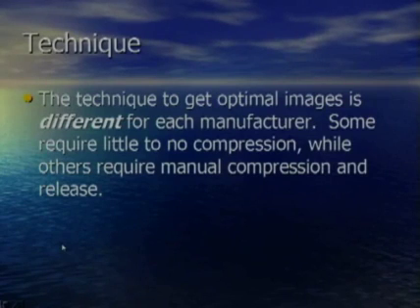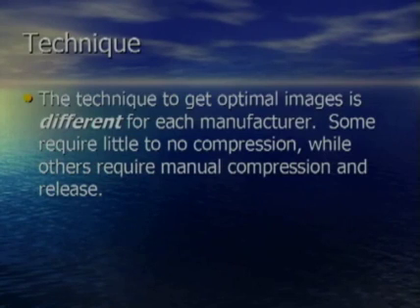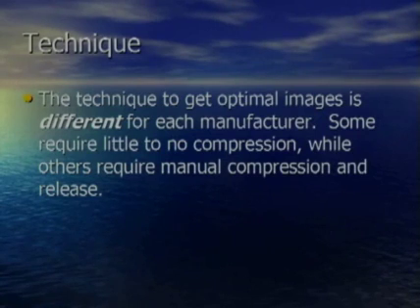Technique is very important in getting optimal images, and the technique actually changes based on manufacturers. Some manufacturers' equipment requires very little or no compression, while others require some manual compression and release to generate an appropriate elastogram. So one manufacturer's equipment may get an optimal image where, using the same technique on another manufacturer's system, you may not even generate an elastogram.